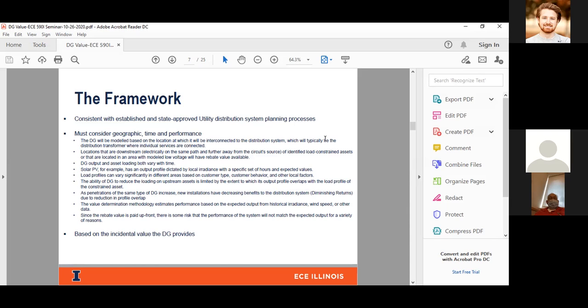The last key philosophy that we wanted to incorporate is for folks to understand that this framework is based on the incidental value that the DG provides to the system. Meaning, if I am a residential customer and I put solar up on top, the utility has no control over my asset. It's just going to operate however I've set it up, west facing, south facing. If I have a battery and a specific mode of operations for it, the utility has no control over it. So it's the incidental value of how I operate the asset and how it ends up providing value to the grid that is captured in this framework.